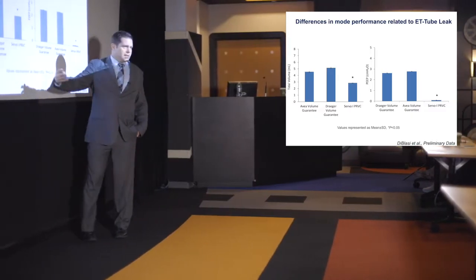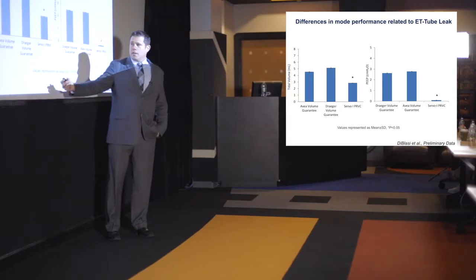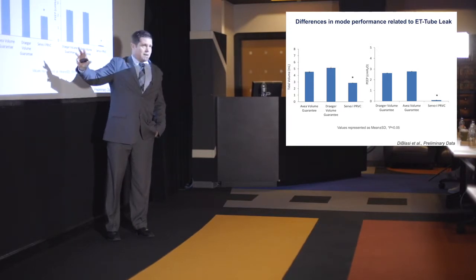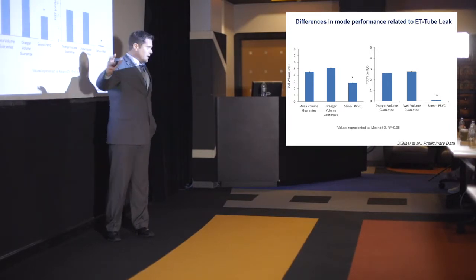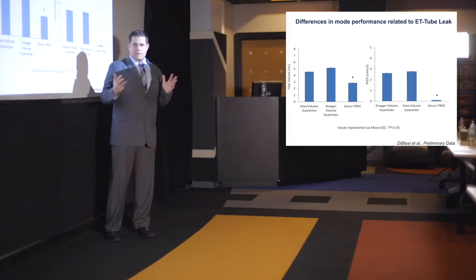And so my friends call me all the time, like, how come I can't do PRVC very well in the NICU with these kids with a leak? I'm like, well, if they don't have a leak, you're probably fine, but let's test it. Let's find out what's going on. And so we took it in a lung model, and this is about a 50% leak at 20 centimeters of water pressure. And we set the tidal volume at around 6 mLs, so super small, like a 1 kilo baby, in an ASL 5000 test lung.